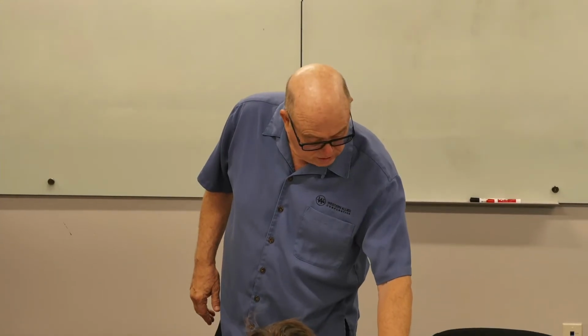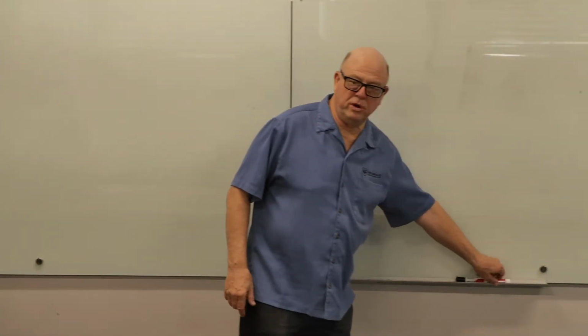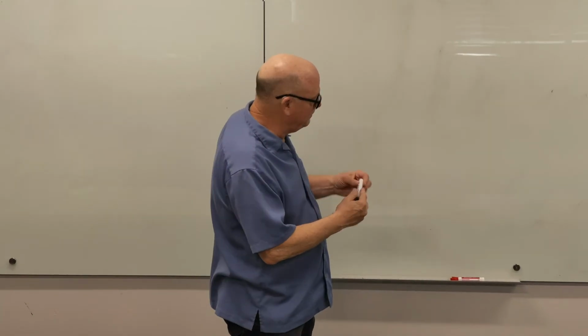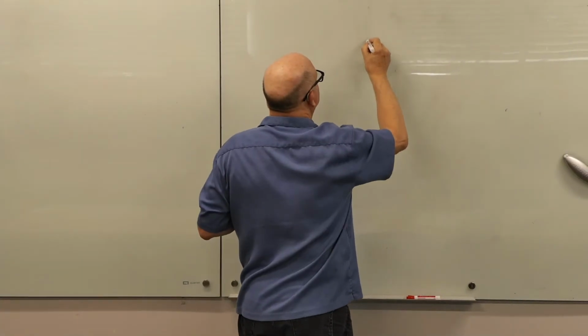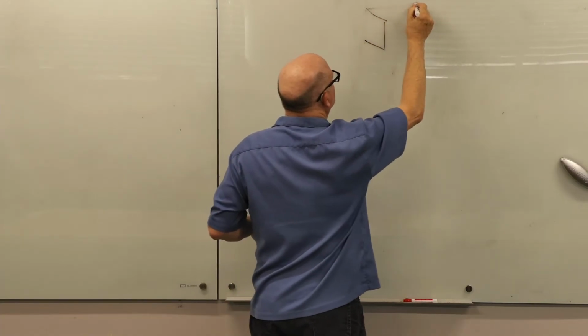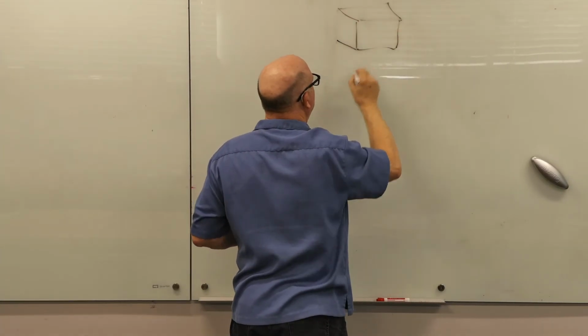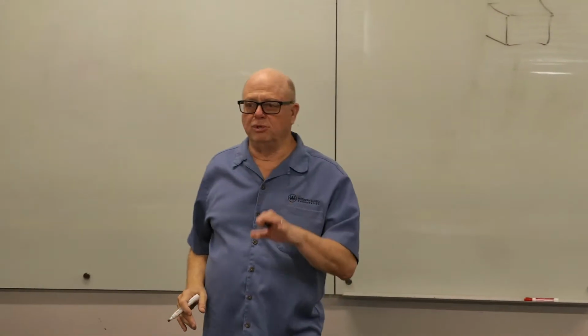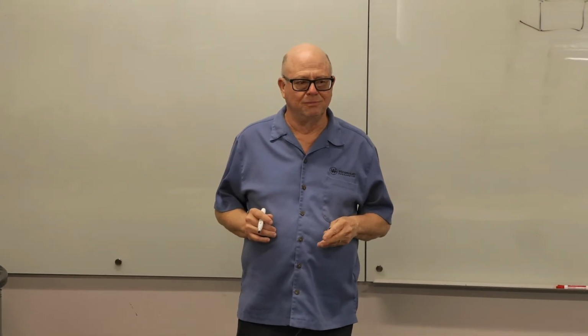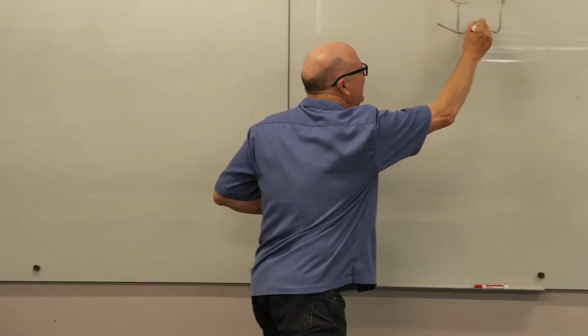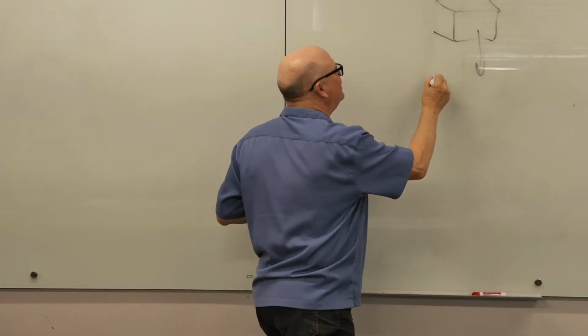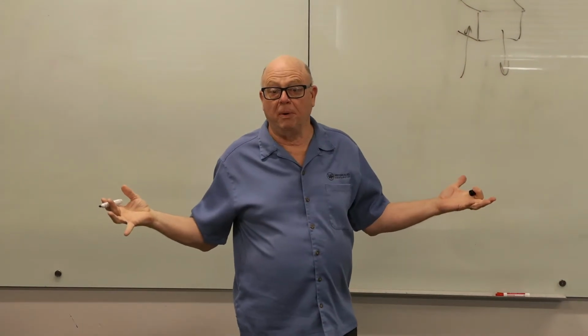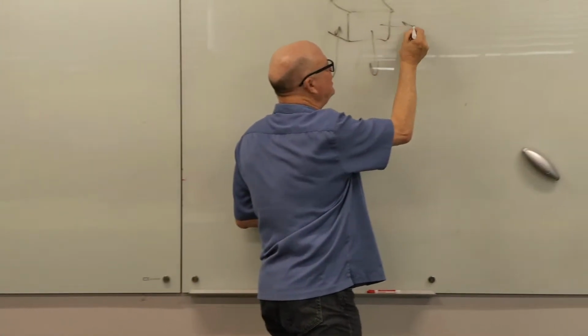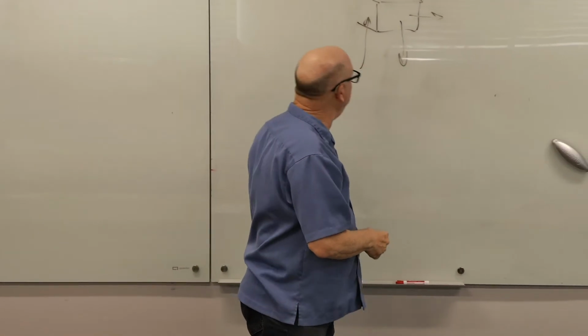The next thing where we left off was curbs, roof curbs. Let's talk a little about roof curbs. The typical cheapy rooftop unit, 5-ton, 10-ton, whatever, is usually called a downshot. Why do you suppose it's called a downshot? Because the air is going down and the return air is coming up. That's as opposed to a side shot, where the air is going sideways. Downshots are on curbs.